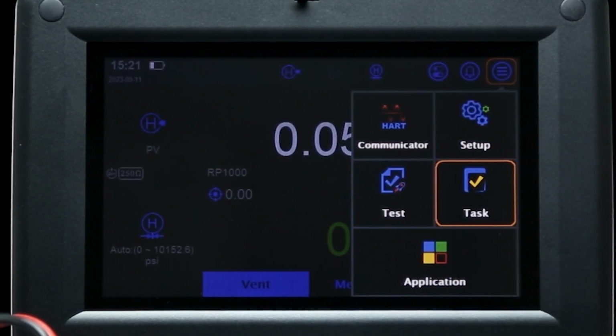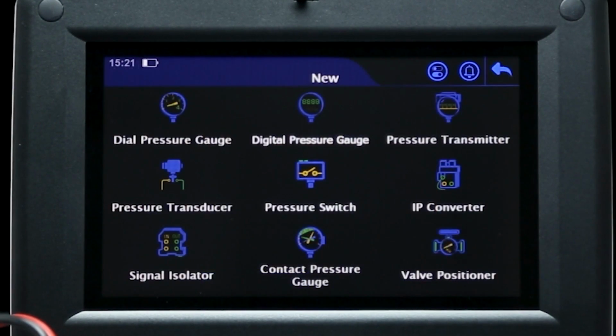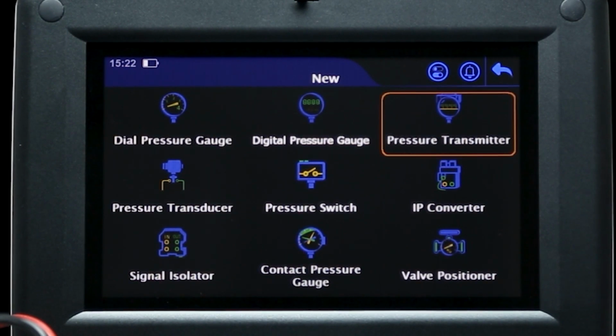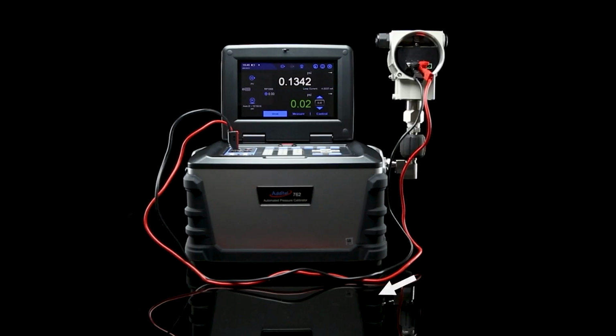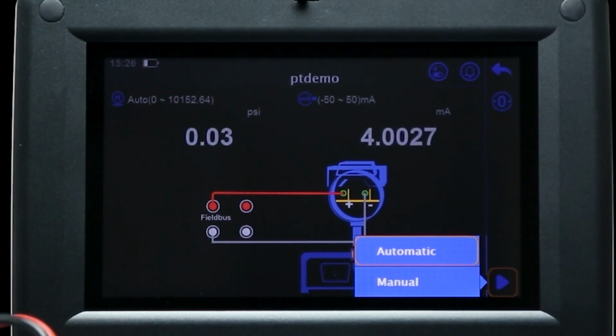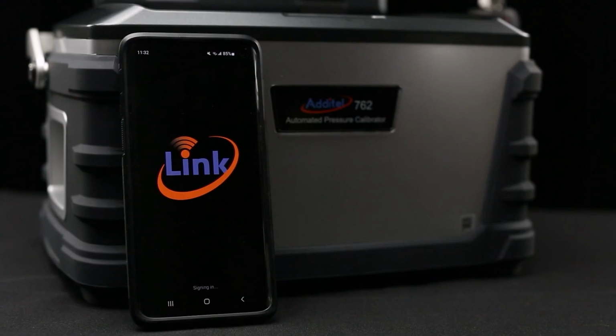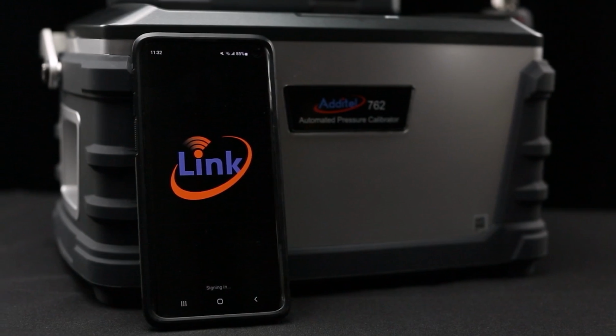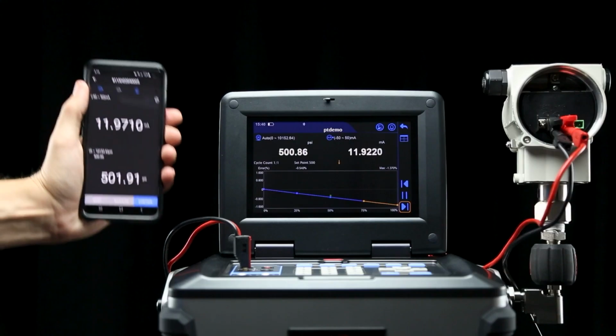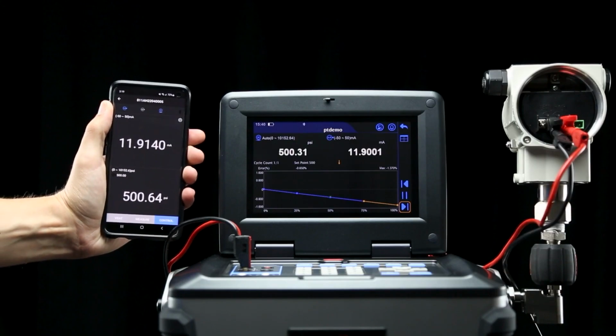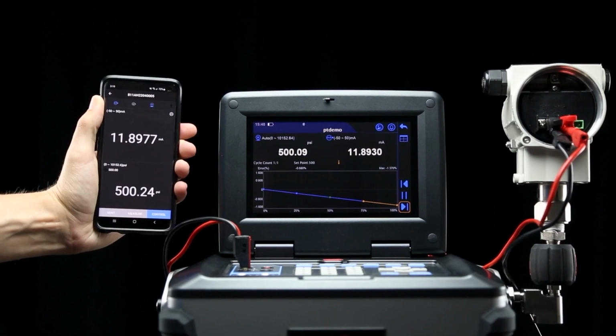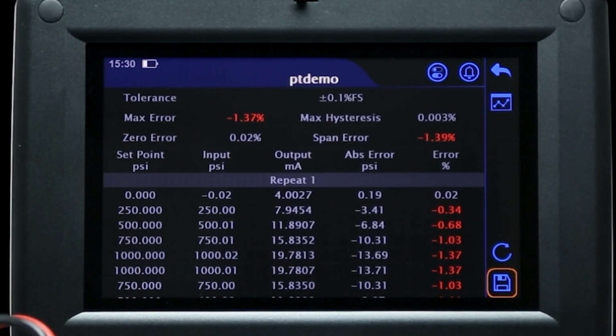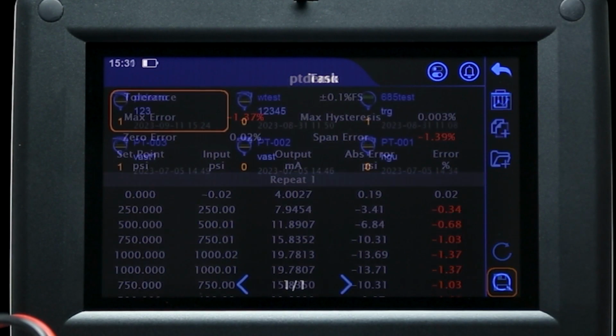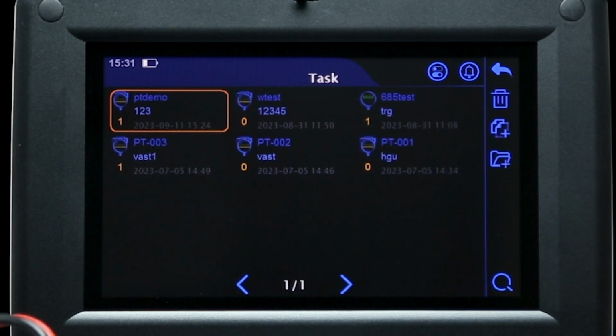Now we will create a task for the transmitter using the same process as we did for the pressure gauge, but instead selecting pressure transmitter from the device screen. Since the transmitter can relay a signal back to the 762, you can now run an automatic calibration at the press of a button. This calibration process can also be viewed remotely using the Additel Link app, which can be connected to the 762 using Bluetooth communication in the settings menu. After the test is complete, the data can be saved or exported, and the task will be saved in your task library for future testing.